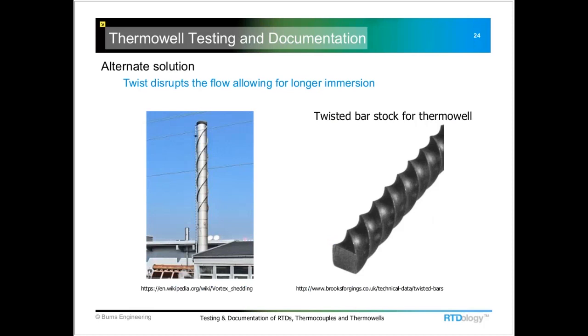Thermowell is the same way, so we can use a twisted bar stock, for example, and this would probably be drilled out for the temperature probe. I know of at least one manufacturer that offers these now. And it seems like a fairly good idea for those situations where you need more immersion length, but you do have a wake frequency issue with a cylindrical thermowell.